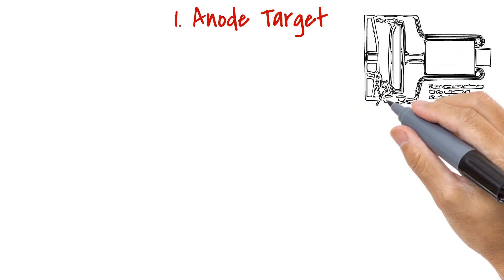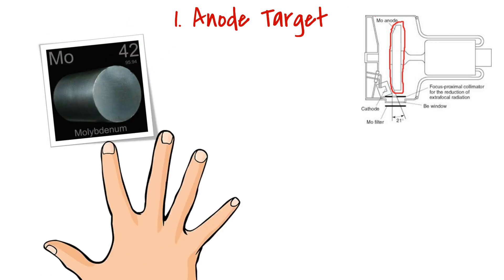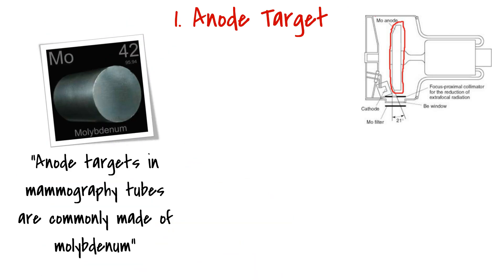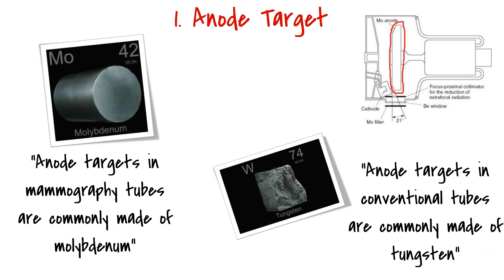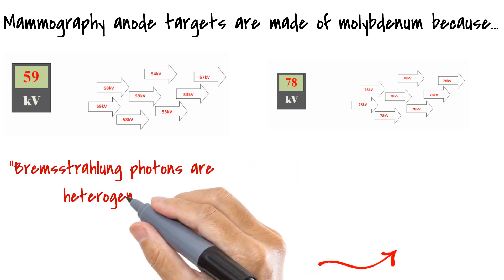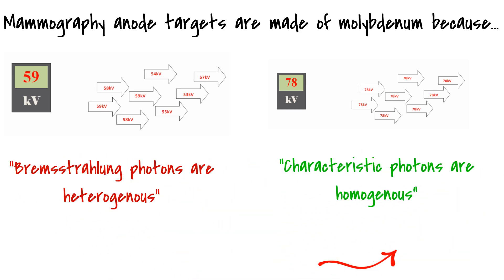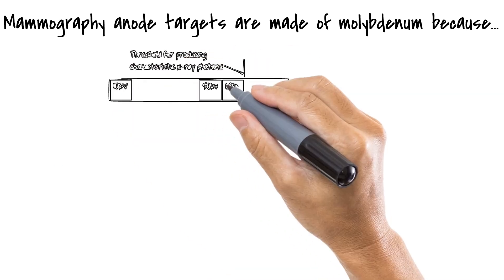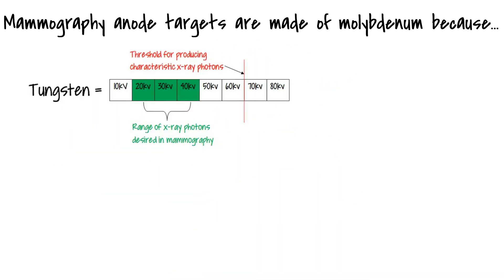Let's start with the anode target. In mammography tubes, the anode target is commonly made of molybdenum, unlike in conventional tubes where anode targets are most commonly made of tungsten. In our video on X-ray production, we learnt about Bremsstrahlung and characteristic X-ray photons. While Bremsstrahlung photons vary in their kilovoltage, characteristic X-ray photons are uniform in kilovoltage and have a narrow spectrum. With tungsten, at least 70 kilovolts is required to produce characteristic photons. Since mammography is always working far below 70 kilovolts, if tungsten targets were used, characteristic X-ray photons would never be produced.